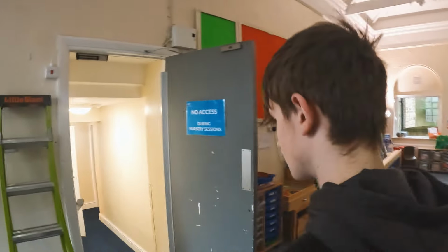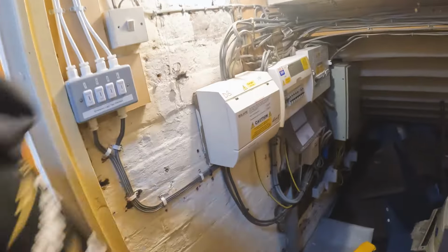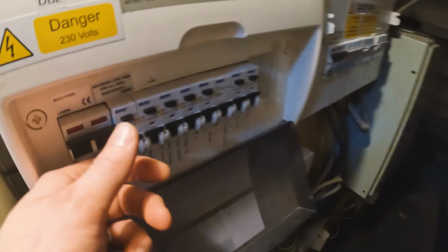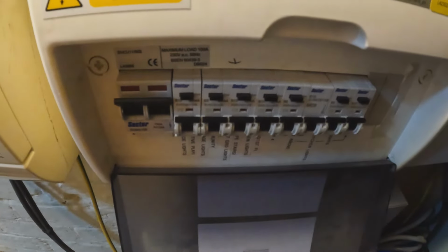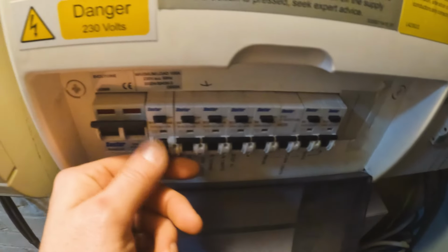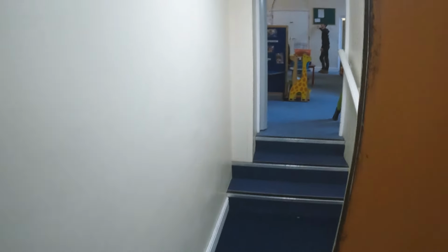So we'll turn on all the lights now, and any light that we can't turn on is stuff we need to look into, isn't it? That's step one: identifying what we need to look into. So you've identified it is that circuit. Let's turn it back on and try to turn everything on in the building, and when it trips again, we'll know which light was on and now it's off.